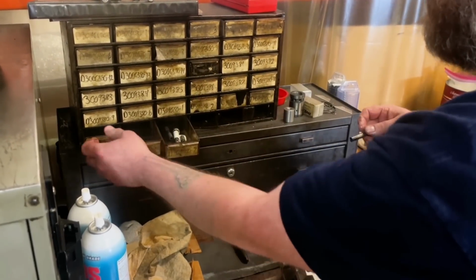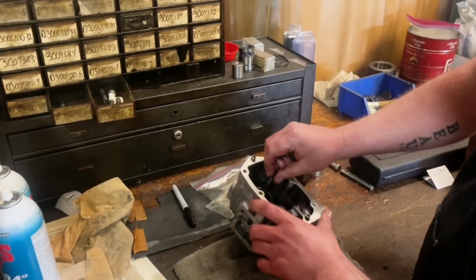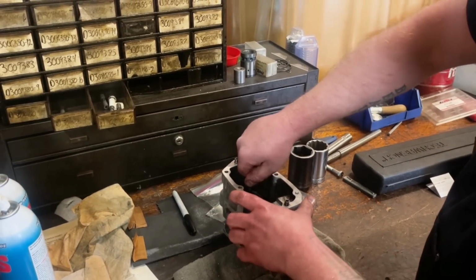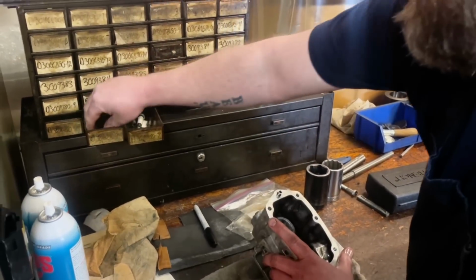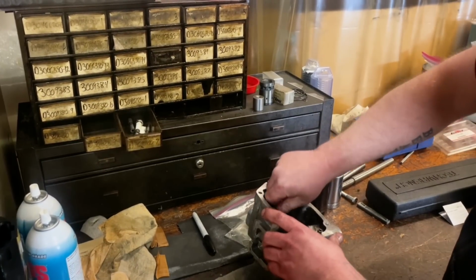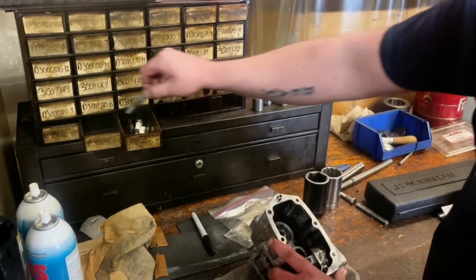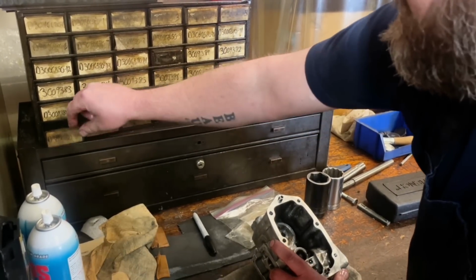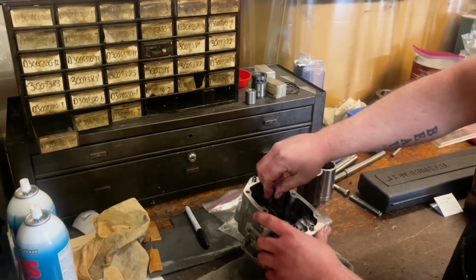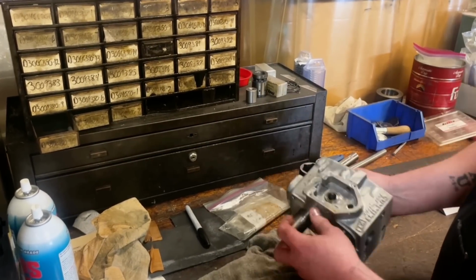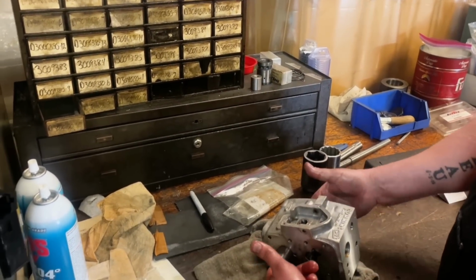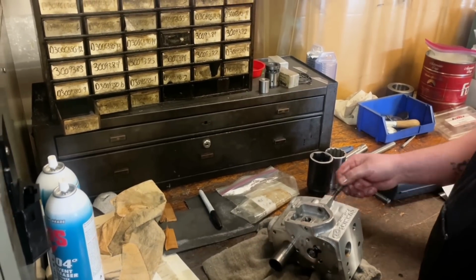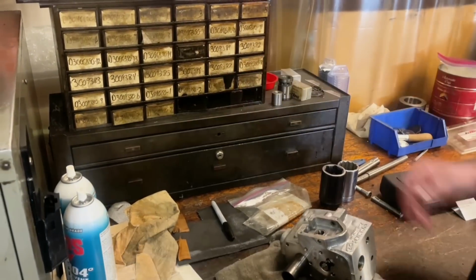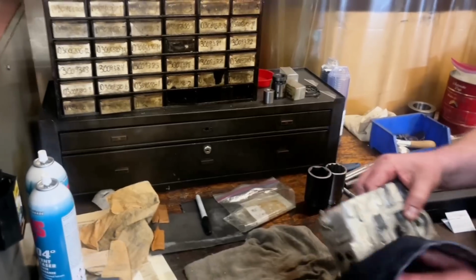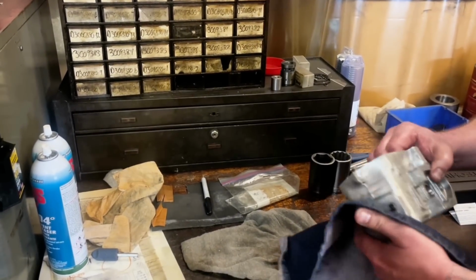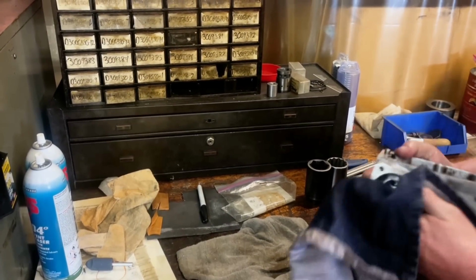Same with the plunger. I got all these different sizes. I'm going to go to one. That one doesn't fit, so we try the next size down. That one fits, so we go 2 sizes down from that, and that's our plunger right there. Make sure it goes back and forth. That's how we fit them - find the one that fits tight and go 2 sizes under, and that's the proper clearance for your shaft and plunger.